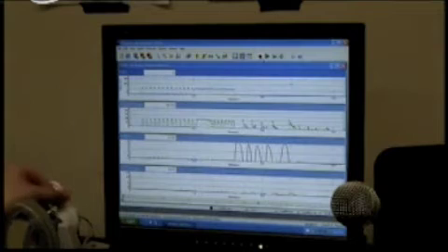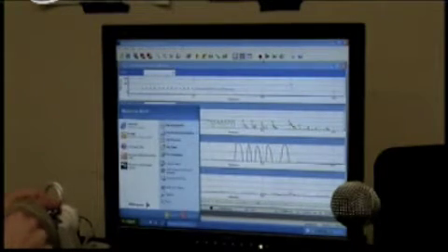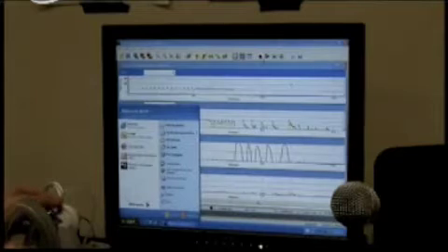Okay. Here, so. The problem you never know is what's the ambient pressure, what's your elevation, things like that. And so doing a 1 liter calibration tells you this system is handling 1 liter as it's supposed to handle 1 liter. Right. We don't know that now. But we're still able to collect data.